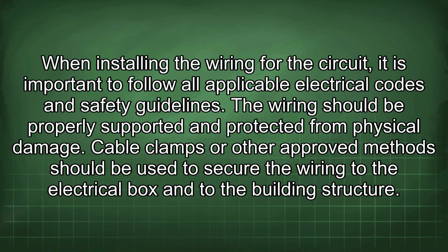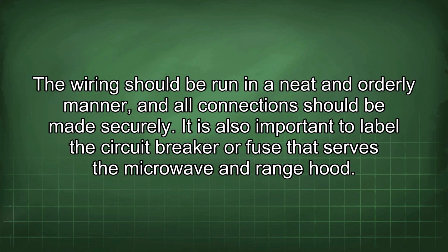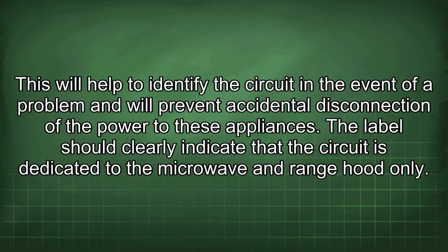When installing the wiring for the circuit, it is important to follow all applicable electrical codes and safety guidelines. The wiring should be properly supported and protected from physical damage. Cable clamps or other approved methods should be used to secure the wiring to the electrical box and to the building structure. The wiring should be run in a neat and orderly manner, and all connections should be made securely. It is also important to label the circuit breaker or fuse that serves the microwave and range hood. This will help to identify the circuit in the event of a problem and will prevent accidental disconnection of the power to these appliances.